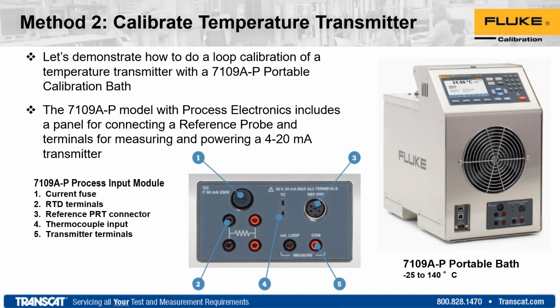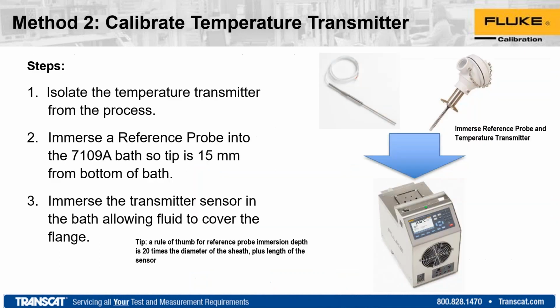So again, if we were to set this bath at 0, run it down and connect up the sensor itself, we would see that it would be outputting 0 versus 100 ohms, and then 135-ish, 140 ohms at 100. So again, just a different way to isolate that transmitter and do a good test. Again, here we made reference to the reference probe versus the immersion depth of the sensor. Again, you never want to have the sensors that you're testing touching the actual bath. You want the fluid to circulate around them.